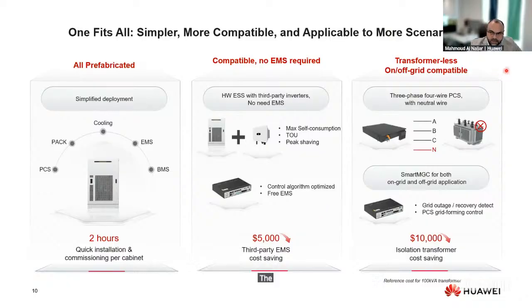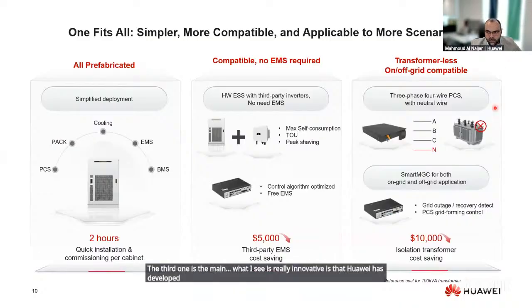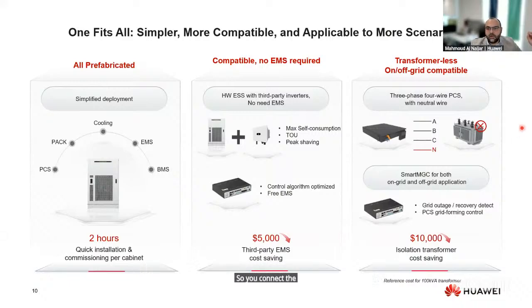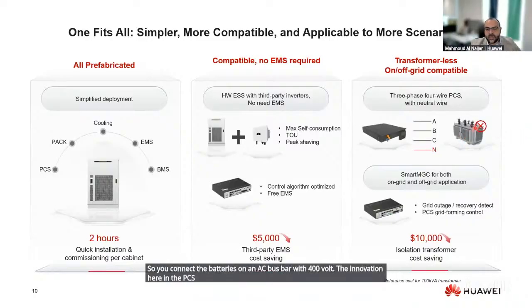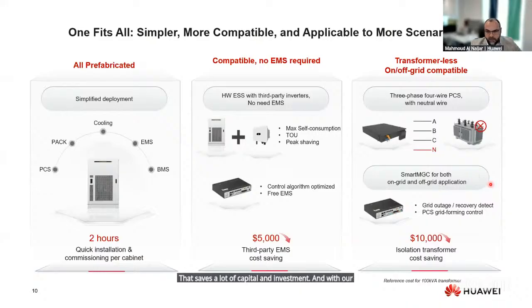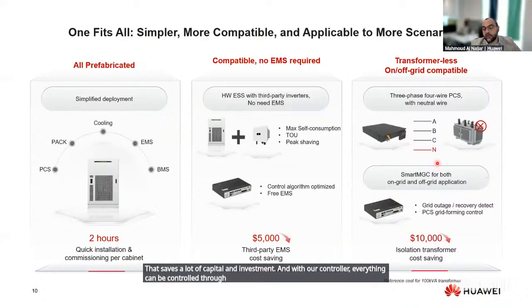The third one, which is what I see as really innovative, is that Huawei has developed a 4-wire PCS. PCS is the power conversion system that converts the power from DC to AC. So the whole system is AC coupled: you connect the batteries on an AC bus bar with 400 volt. The innovation here in the PCS is that it provides 3-phase and a neutral. So you don't need to install any external delta-Y transformer or isolation transformer to provide the neutral point. That saves a lot of capital and investment. And with our controller, everything can be controlled through our MGC. That also saves extra components that would be required and reduces your capex.